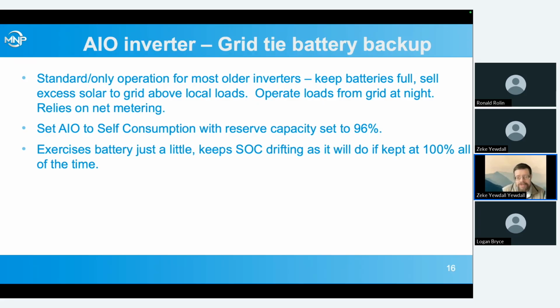So the way to solve that is we put the all-in-one inverter in self-consumption mode and set our reserve capacity down just a little bit below 100%. I usually pick 95, 96%. And what this does is it exercises the battery just a little bit each night without really draining it much. In the morning, the BMS says, I'm not at 100% anymore, because it's actually pulled it down at a higher rate by running the loads a little bit until it got down to 96%.